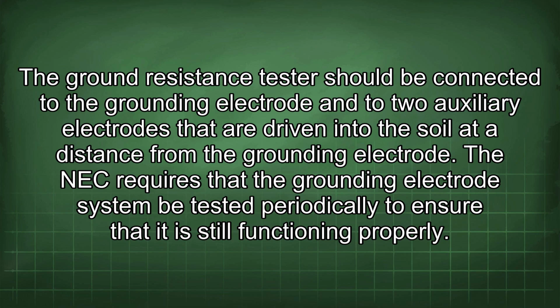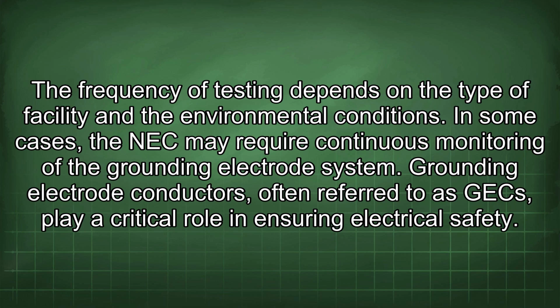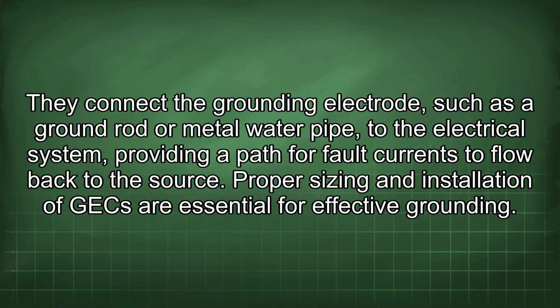The NEC requires that the grounding electrode system be tested periodically to ensure that it is still functioning properly. The frequency of testing depends on the type of facility and the environmental conditions. In some cases, the NEC may require continuous monitoring of the grounding electrode system. Grounding electrode conductors, often referred to as GEC, play a critical role in ensuring electrical safety. They connect the grounding electrode, such as a ground rod or metal water pipe, to the electrical system, providing a path for fault currents to flow back to the source. Proper sizing and installation of the GEC are essential for effective grounding.